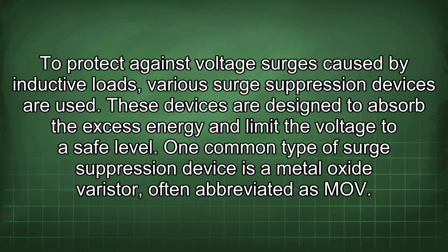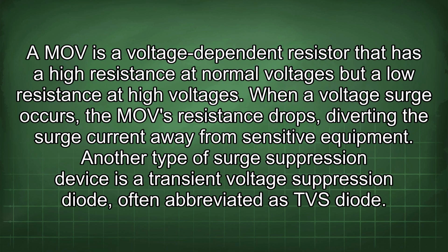To protect against voltage surges caused by inductive loads, various surge suppression devices are used. These devices are designed to absorb the excess energy and limit the voltage to a safe level. One common type of surge suppression device is a metal oxide varistor, often abbreviated as MOV. An MOV is a voltage-dependent resistor that has a high resistance at normal voltages but a low resistance at high voltages. When a voltage surge occurs, the MOV resistance drops, diverting the surge current away from sensitive equipment.